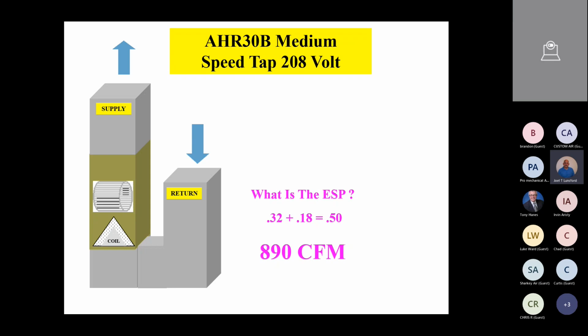So this is a 2.5 ton air handler, medium speed tap. It's probably on a 2 or 2.5 ton unit. If it's matched up with a 2 ton unit, we're blowing a little bit more airflow than we normally would, because we want to always build our duct systems, fellas, to provide 400 CFM per ton. And so if we had this on a 2-ton unit, we're blowing a little bit too much. If it was on a 2.5-ton unit, we're a little bit light on airflow. So you guys get the idea.